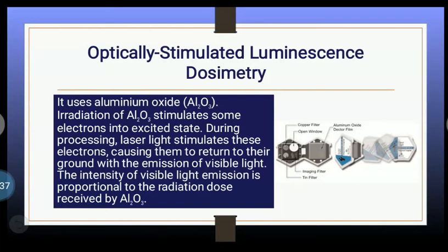Halimbawa ako, ganito yung dose na na-receive ko, si Camille ganito, si Rachel, ganon yung na-receive niya. So, that control badge will confirm na talagang ganon yung na-receive ninyong dose. So, 1 control badge for every unit, for every machine sa inyong department. And then, 1 TLD, or if you are using OSL, for every working radiologic technologist sa department.